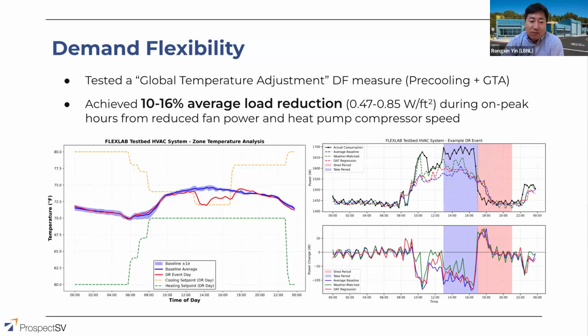Just a very quick recap of our demand flexibility testing. We only implemented the global temperature adjustment DF measure in our test bed: pre-cooling during the mid-peak period from 12 to 4 o'clock, and between 4 and 9 o'clock we just raise the set point by 4 degrees. This is the power response on the system side, and roughly we got 10 to 16% of load reduction during the on-peak period. It's just for the temperature adjustment testing measure. We haven't incorporated any thermal storage in this demand flexibility testing.